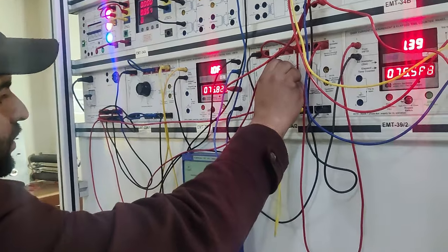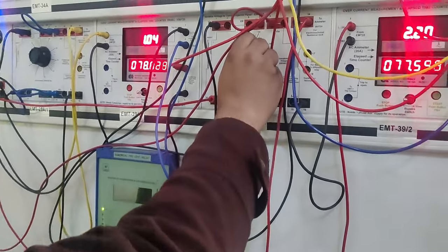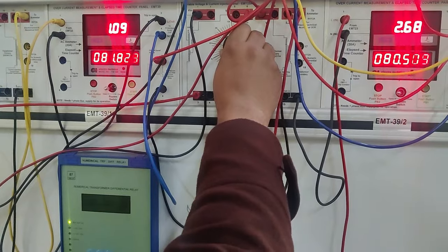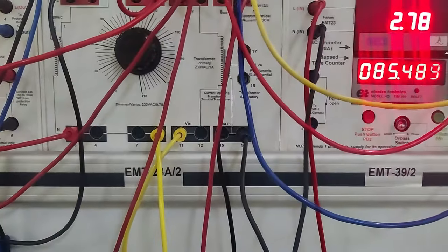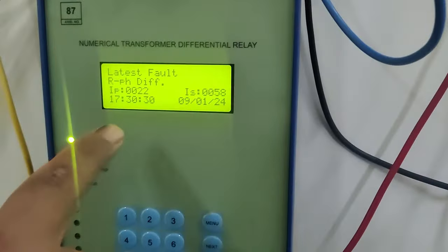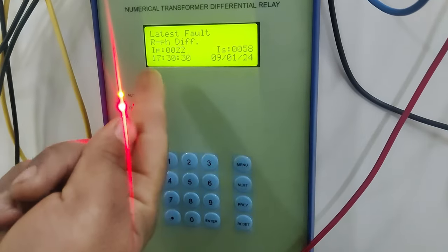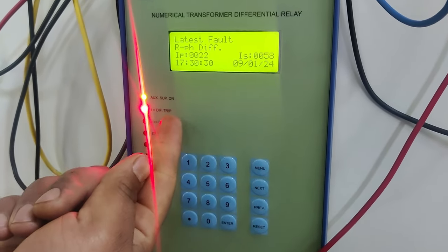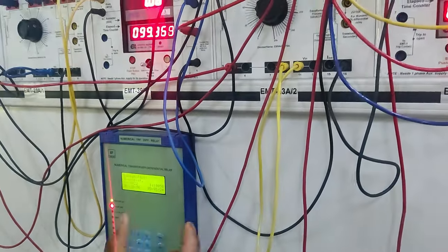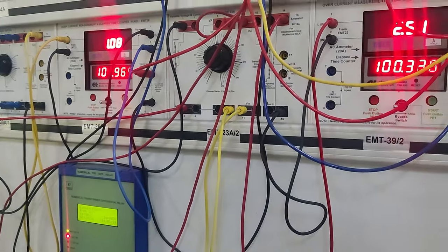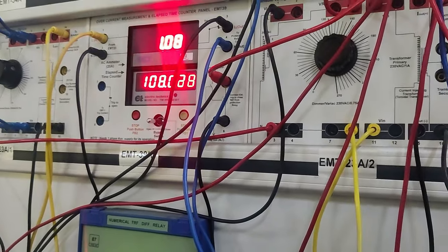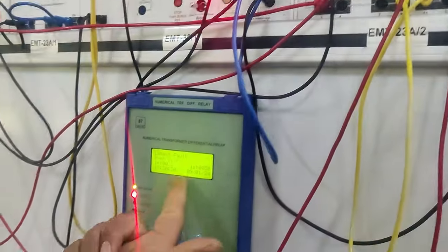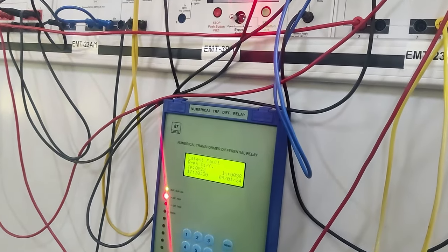I will increase this current — you can see it increasing. It has reached 2.45, and at 2.77 amps the differential relay has got tripped. You can see it has shown that I is greater than the differential trip — that means the difference of the two currents is now around 1.8 amps, which is in per unit equal to 0.2 per unit. It is very fast. You can see it is showing the current and the date at which the differential relay got tripped.